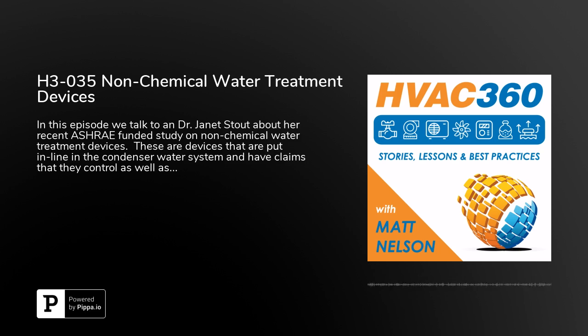Okay, so let me see if this is a fair way to boil it down: you're basically testing the sump of the cooling towers, and you're testing the equivalent of the fill by means of that coupon. So you're actually testing the bio slime or the film on a coupon that would be similar to what you'd find on the packing material, correct? Yes, absolutely. And both are very important in terms of heat transfer.